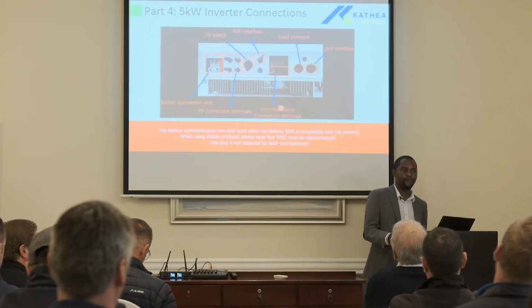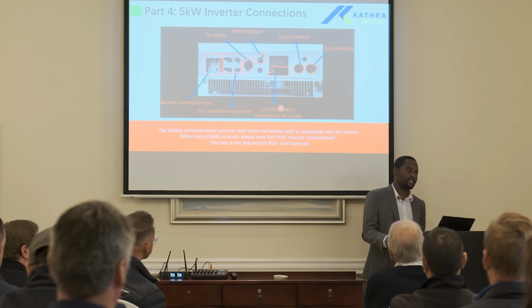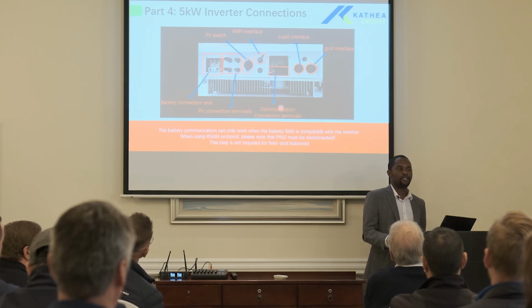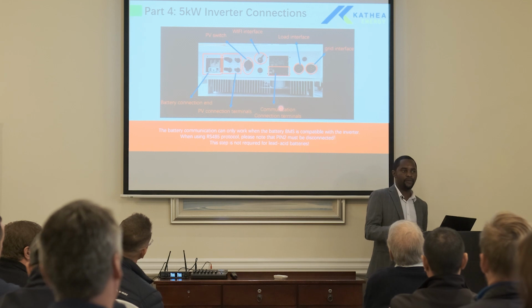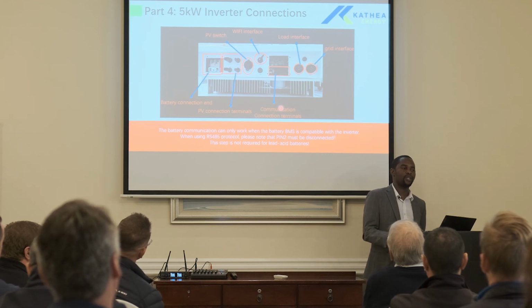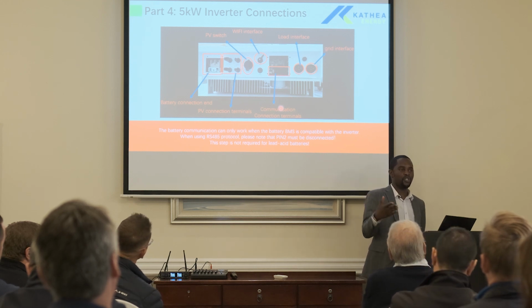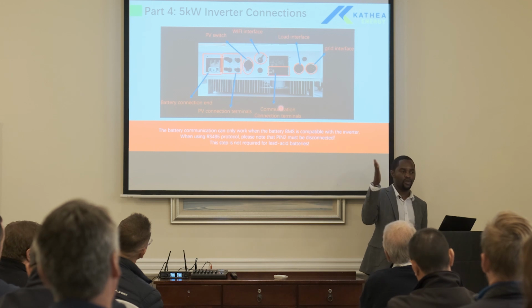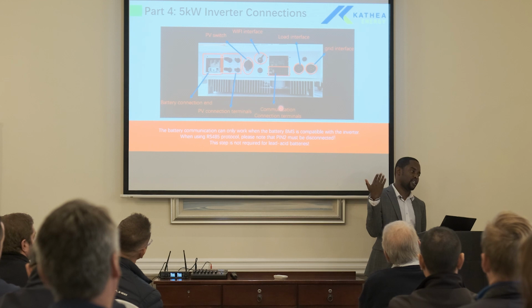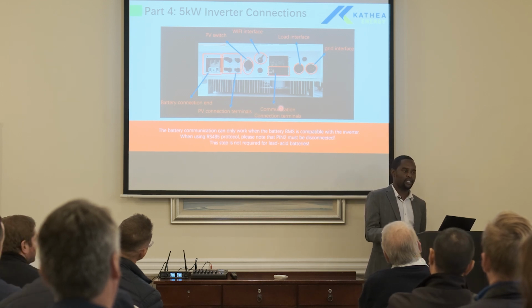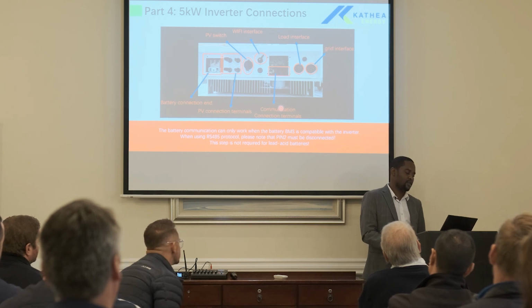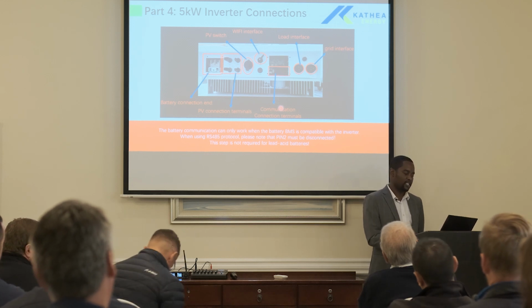Say 15 amp, the current rating of the MPPT, 30 amp per MPPT, then 15 per each string input. Then if you want to exceed the amperage, you can actually go up to 20 on one string input, but now you won't be able to use the next string input. So it's 2 MPPTs, which means you can have 2 different roof facets. You can actually have your north and east facing. Then make sure that you wire them on their separate MPPT. Otherwise, if you mix, then the least producing string will pull down the one that might be producing more.